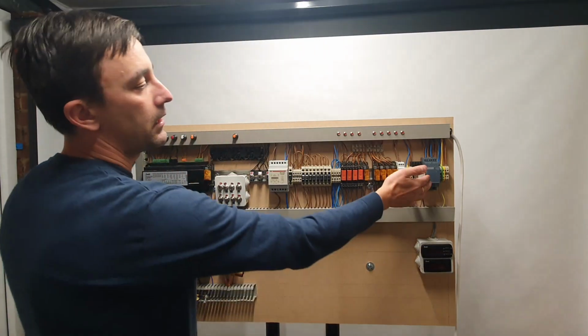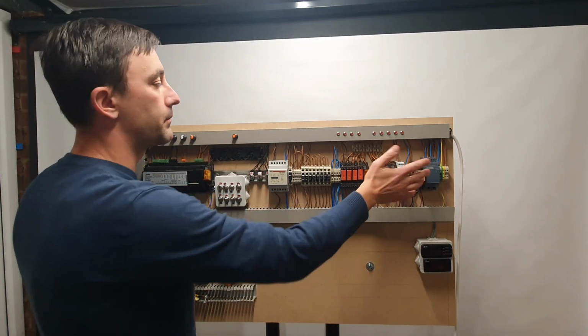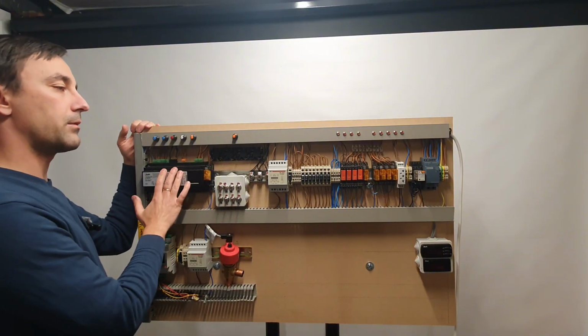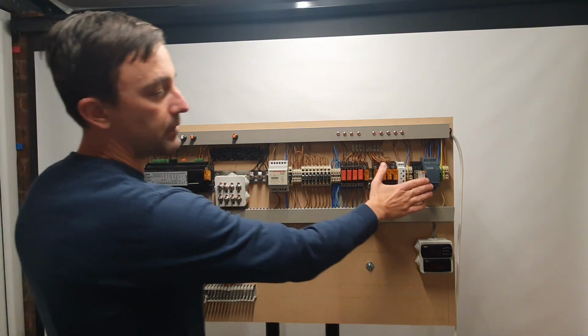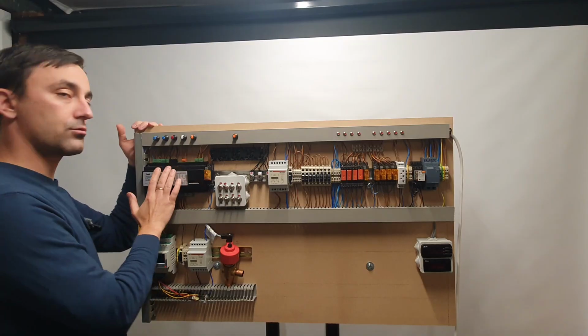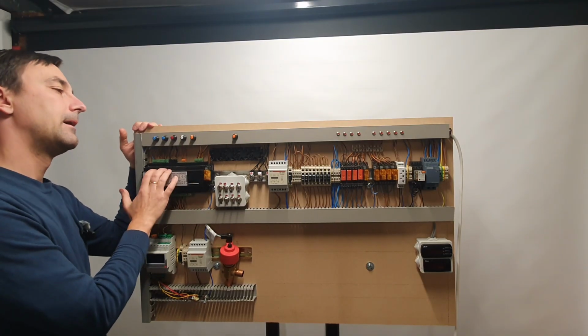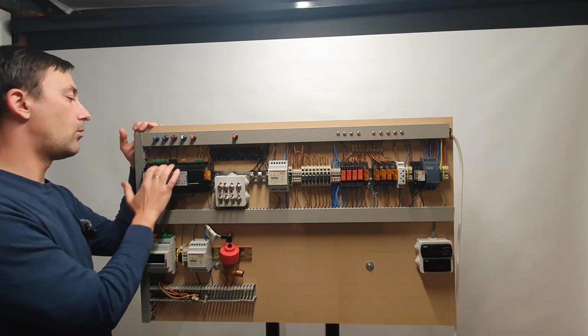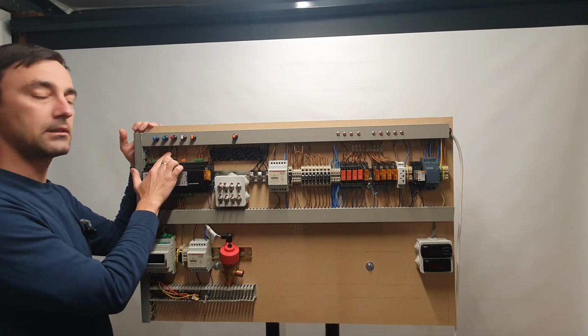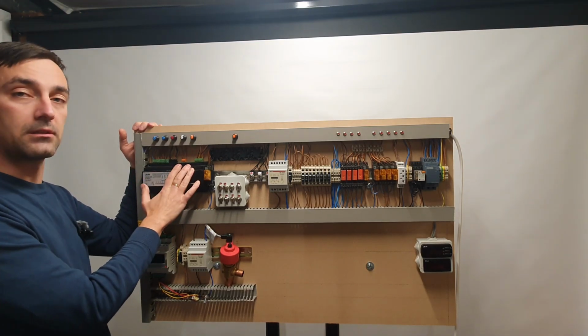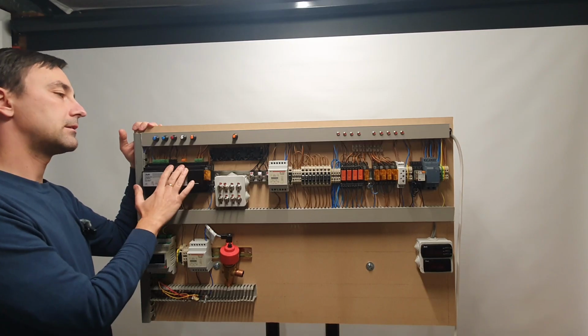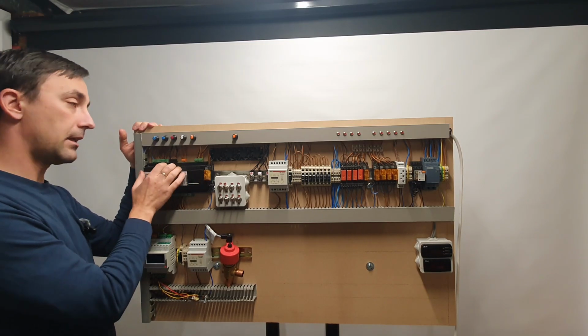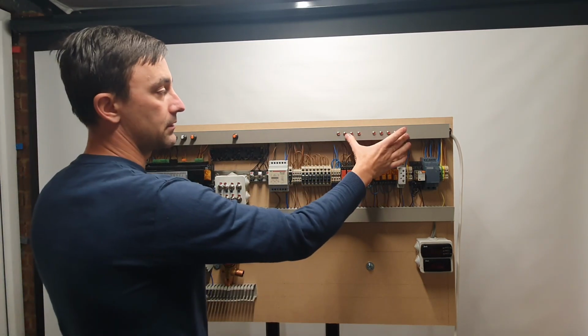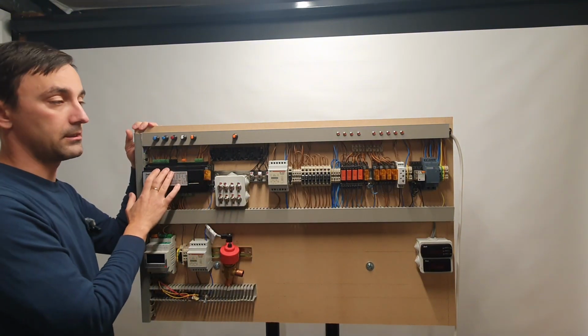And here we have a condenser fan relay, but for the setup I chose, it's not being used because this controller, unfortunately, only gives the signal to the condenser fans, the 0 to 10 volt signal I'm referring to. It does not run the condenser fans the way we run the compressors. It's just the way this controller is.